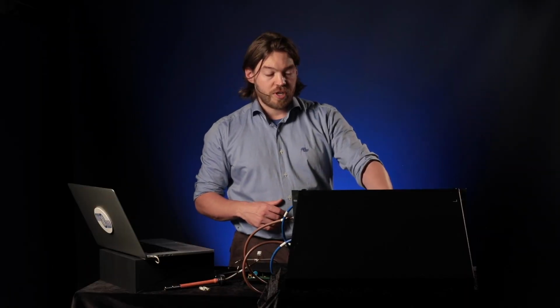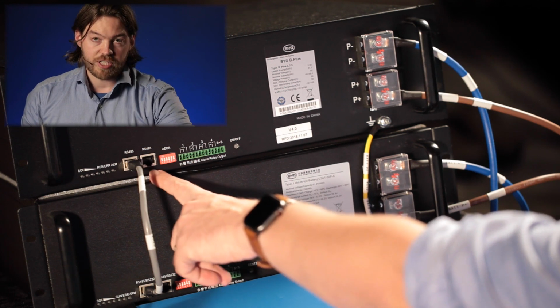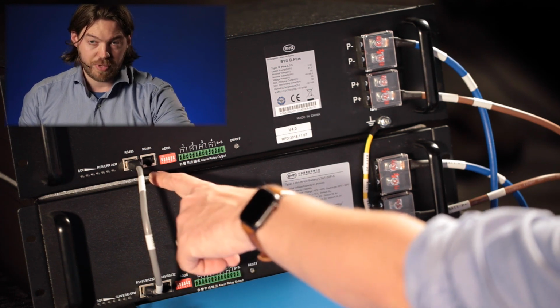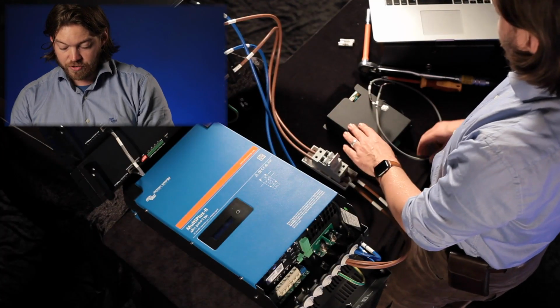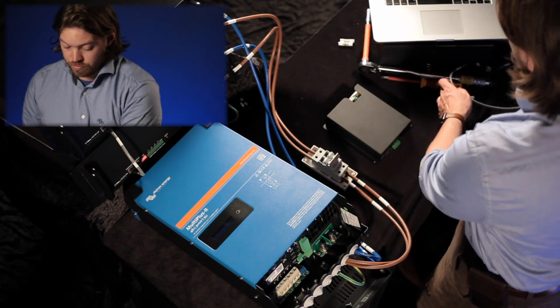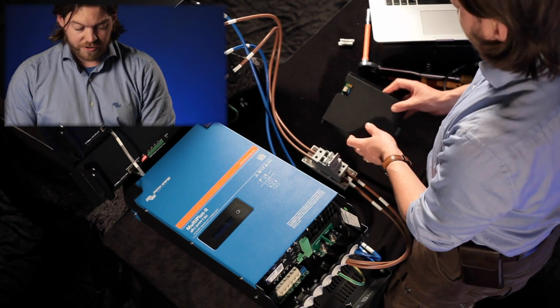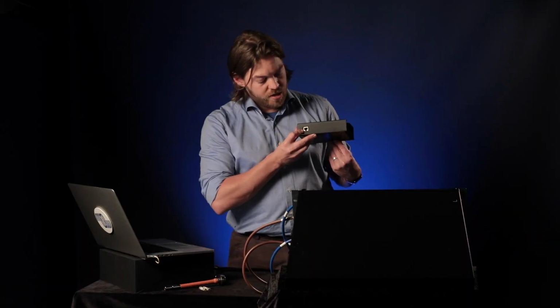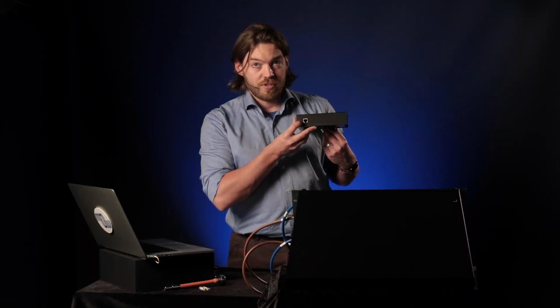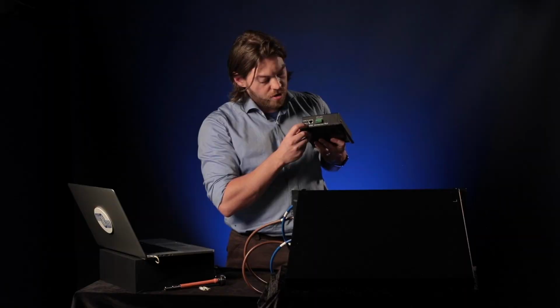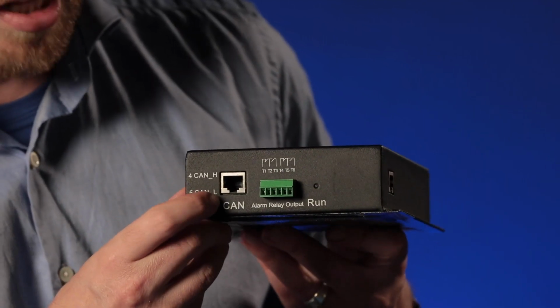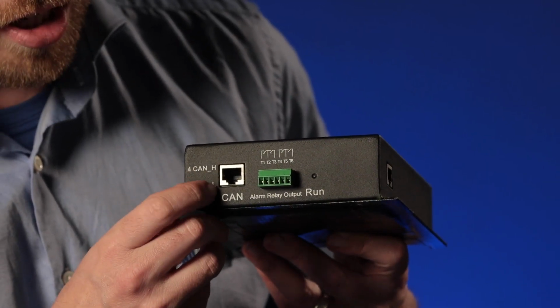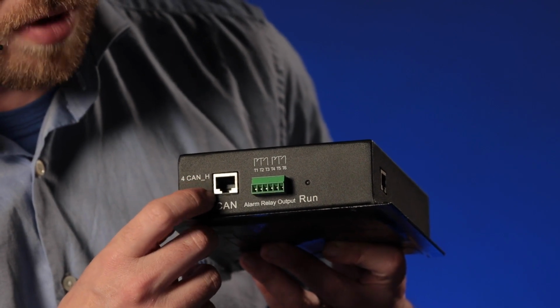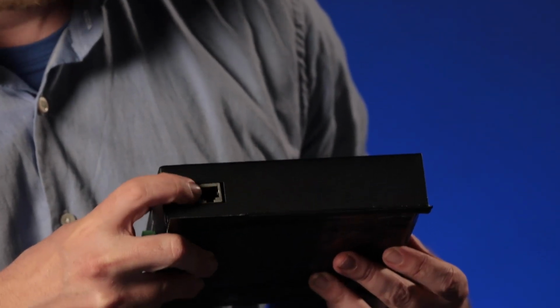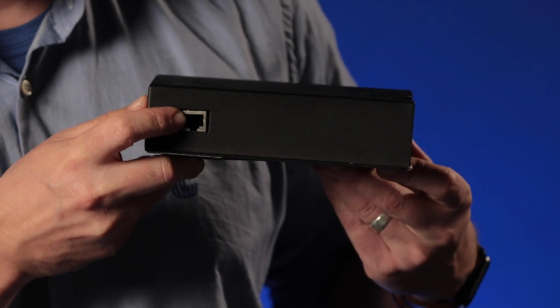The next comms cable we need connects the RS485 port on the BYD battery to the RS485 port on the BMU. The RS485 port on the BMU is the one that isn't labelled. On the front of the BMU we have the CAN cable, labelled with CAN H and CAN L as the active pins. But the unlabelled port is the one we connect our BYD batteries to, the RS485 connection.